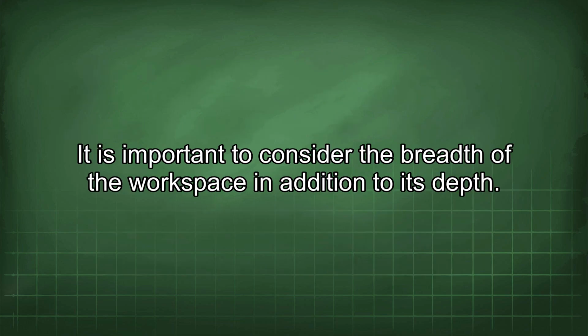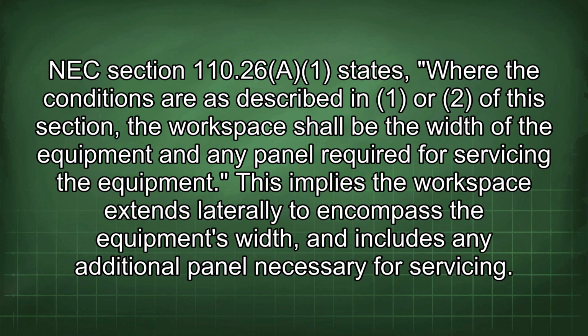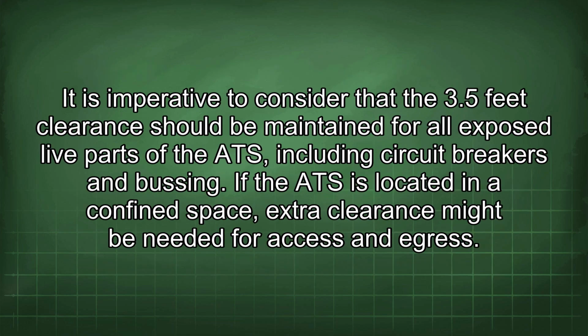It is important to consider the breadth of the workspace in addition to its depth. NEC Section 110.26(A)(1) states, where the conditions are as described in 1 or 2 of this section, the workspace shall be the width of the equipment and any panel required for servicing the equipment. This implies the workspace extends laterally to encompass the equipment's width and includes any additional panel necessary for servicing. It is imperative to consider that the 3.5 feet clearance should be maintained for all exposed live parts of the ATS, including circuit breakers and busing.